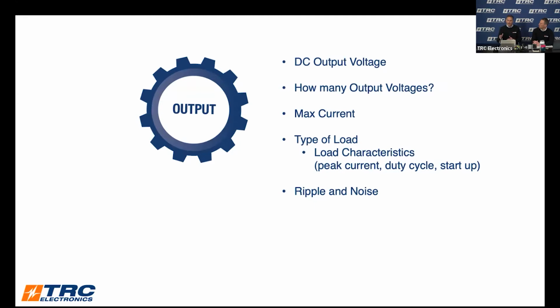If you pick a power supply with hiccup load protection and you need a peak requirement, you might actually put that power supply into perpetual hiccup mode. This is why you need to be aware of the characteristics of your load with the power supply, so that when we look at the protection features, they align with the type of load you have in your application.